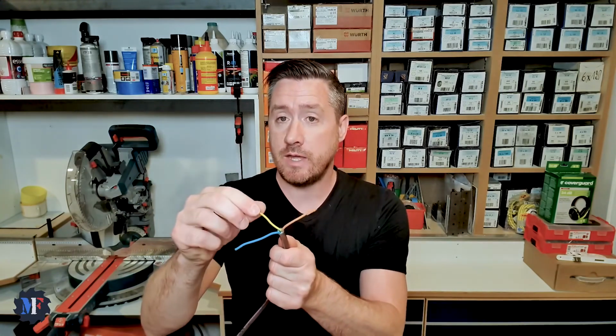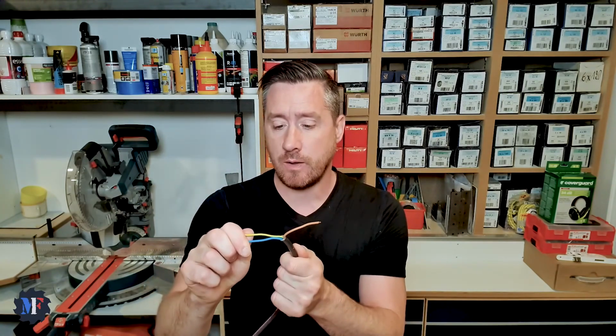Brown, black, red, purple, orange, okay? And it's useful in some cases, for example with a single switch. If you're logical, you don't necessarily need to change the color between the switch and the bulb, although it's recommended. But beyond one or two switches, it's useful to change the color because it's easier to identify. But I repeat, it's very important: blue for the neutral, yellow and green for the ground, that's mandatory.